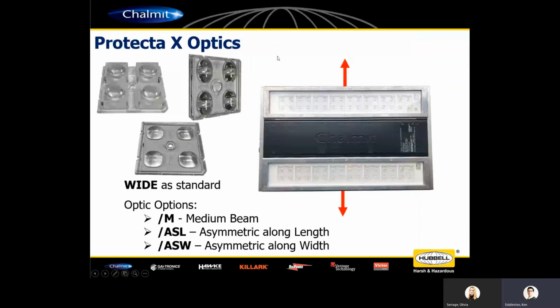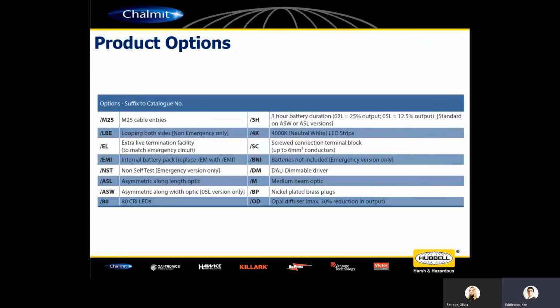Now, not really a requirement for exterior products, but is commonly for interior products where we're trying to limit the risk of the luminaire going through self-test in the middle of the night, potentially while people are sleeping. Okay. The other point to note is regards to the emergency outputs. So if you order the emergency Protecta X, the product comes as 90 minutes as standard. If you want 3 hour, /3H suffix, okay, which will limit the battery duration.